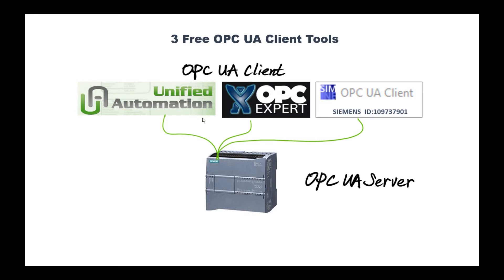Before I start to share those three tools, let's quickly review the settings on the OPC UA server side. This is TIA Portal version 16 software. This controller is an S7-1200, version 4.4. In this project, I set up this controller running as an OPC UA server. In the controller properties, I activate the OPC UA property.